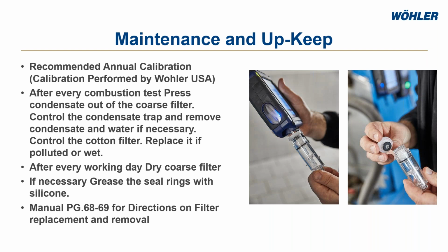We recommend a yearly calibration. Now, obviously, a yearly calibration is pretty standard throughout the market with combustion analyzers. Most of all the other manufacturers also require a yearly calibration, but it's really dependent on how much you use it, I would say. If you're a person that uses it maybe once or twice a year, you may be able to extend that calibration out past a year, but it is by factory recommendation that you get it calibrated every year.